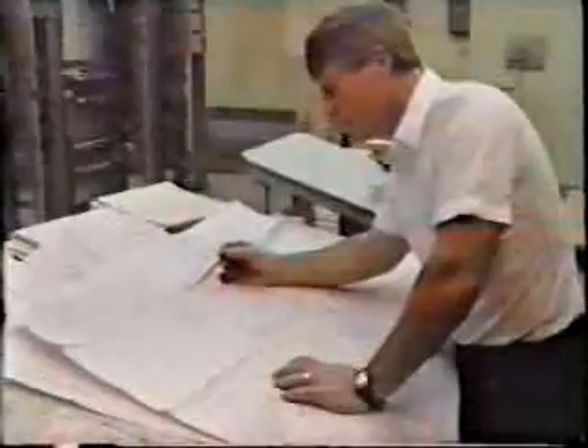It is essential that you thoroughly review the schematic diagrams for each of the protective schemes. Trace through these diagrams to get an understanding of the protection system. If you have any questions, as you probably will, make sure that you discuss these with your supervisor. You may well spot something that could cause problems later on. You should have a separate diagram for each protection and control loop. This is quite different from the wiring diagrams that will be used by the contractor for installation. These installation wiring diagrams are really geographical in nature, and any one diagram, say to a relay panel, may include several hundred connections and involve a multiple number of independent loops. You should check the wiring diagrams against your schematics to prove that the wiring really does achieve what it sets out to do.